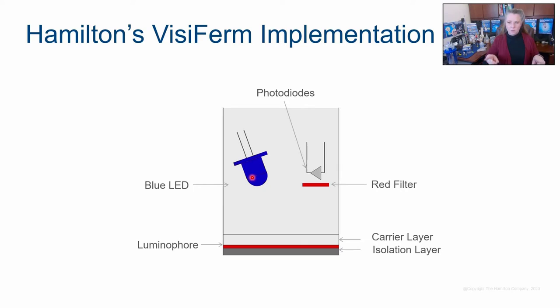Will those light bulbs burn out at the same rate? A year later, 2 years later, will they both burn out at the same time? In my experience, the answer is no. Lights never age at the same rate. And so if you have two lights built in and one of them is your standard and the other one is your measuring and you're using them to compare, you have to continuously adjust through the entire age of the lights.